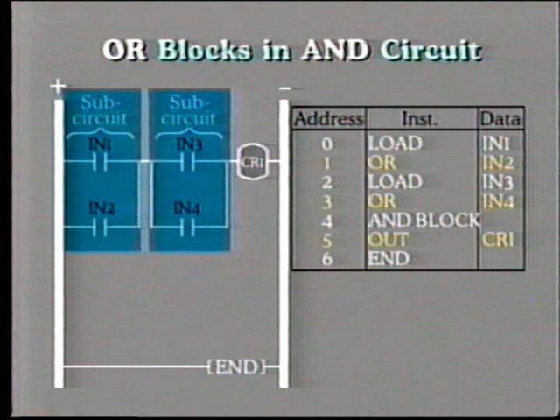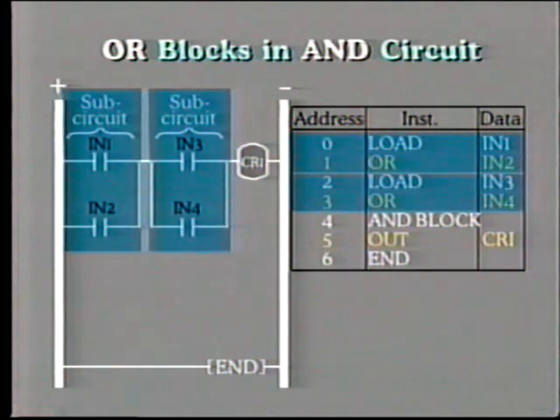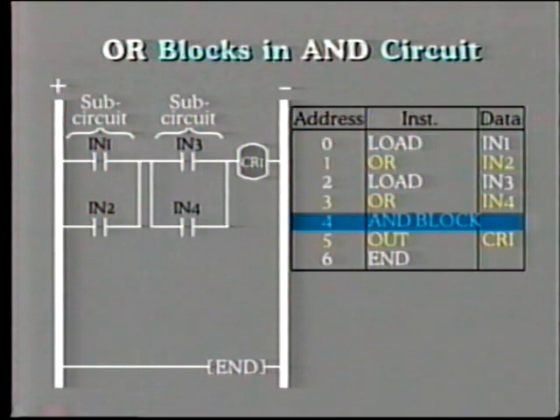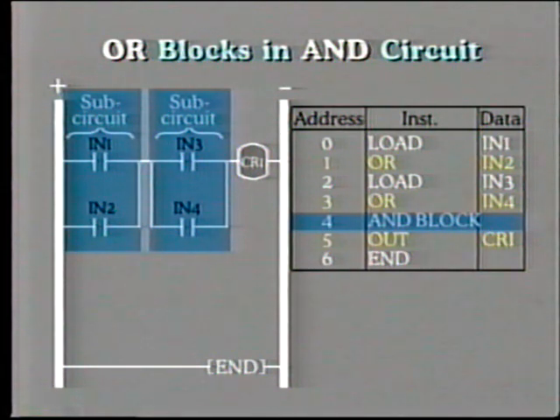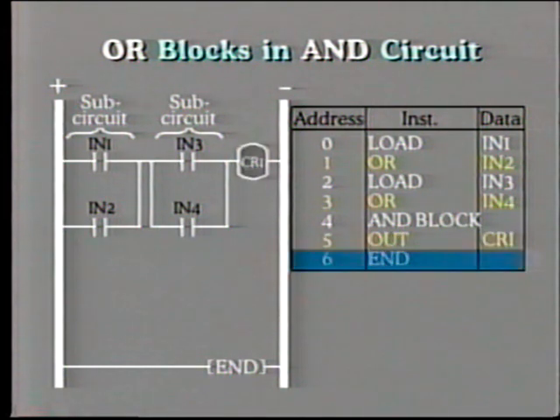Many logic diagrams become quite complex, and in this case, the written ladder code is simplified by using sub-circuits or blocks. For example, here we have two OR sub-circuits which are in series to energize the control relay output. To simplify the ladder code, this is broken down into the two sub-circuit blocks. Address 4 on this ladder does not refer to any particular input or output point, but to an examination which must be performed in the register. To satisfy this condition, both of the sub-circuits, that is the blocks, must be on. This in turn will provide an output to energize the control relay. Note also that an additional address number 6 is added to indicate end of sequence.